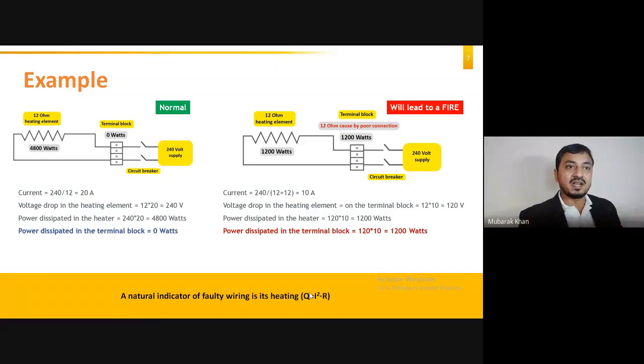What is its effect? What is the problem? Now the issue is, when 1200 watt is dissipated on the heating element, nothing will happen to the heating element because it is designed to withstand a large amount of energy. So nothing will happen to the heating element, right? The only thing is that the heating effect which it is creating will be reduced. It will not be enough, it will not be as much as required. It is only 1200 watts, not 4800 watts, what it was in normal conditions. But your heater will not burn.